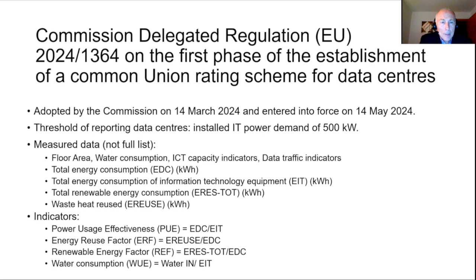This is an important point that is often forgotten. Due to the vast generation of heat by the processors, there is always a need to evacuate this heat from the server room. Traditionally this heat was wasted into the atmosphere via heat exchangers or cooling towers, but in many situations it can be recuperated, reused, and shared, for example with buildings through district heating or district networks, or with nearby greenhouses. So it's very important.